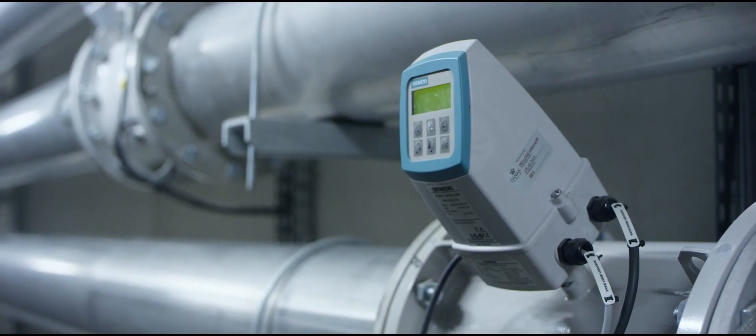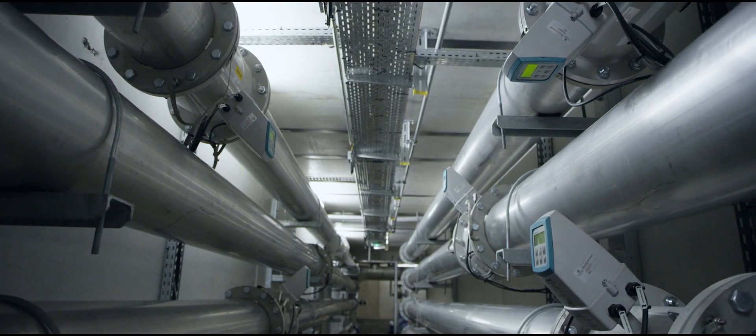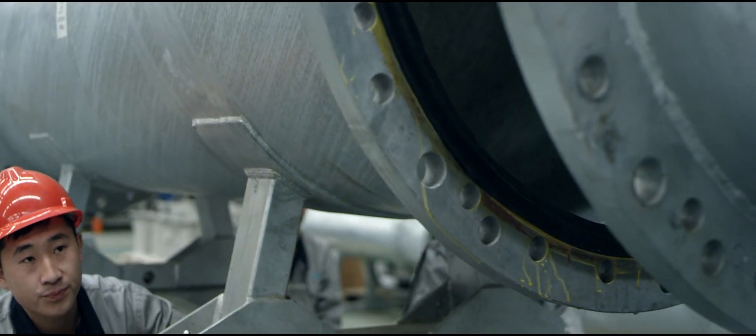So, talking about we have facilities to calibrate up to 3 meters — that means we have to have a 30 meter inlet distance before we place our device under test for calibration.